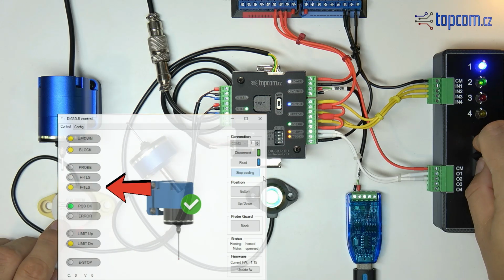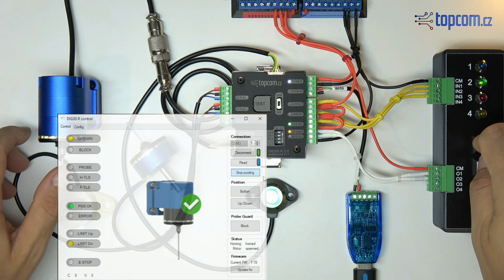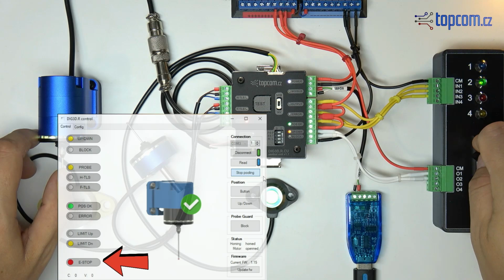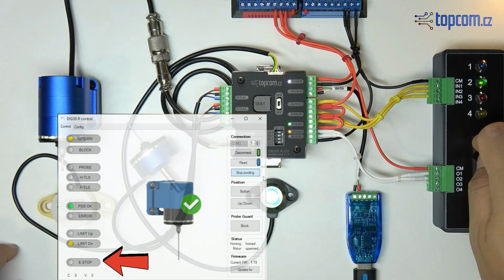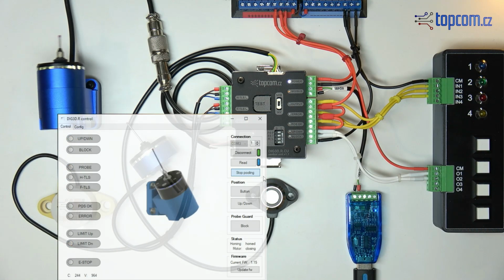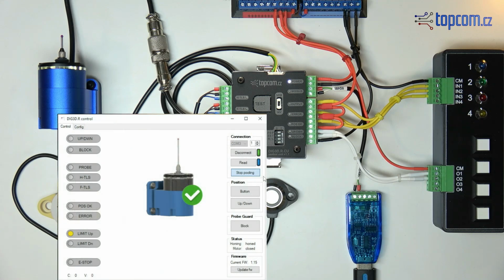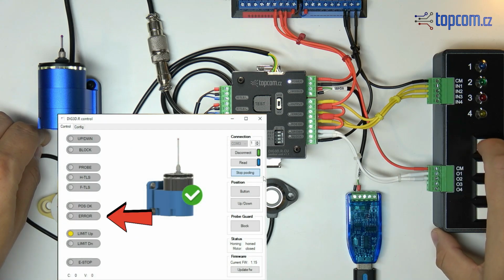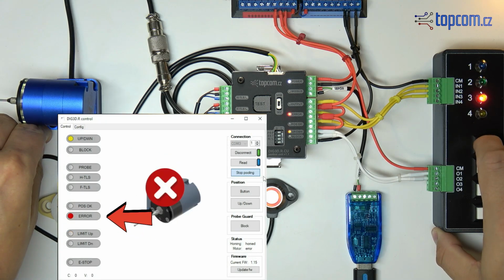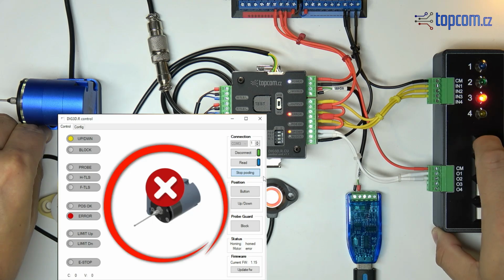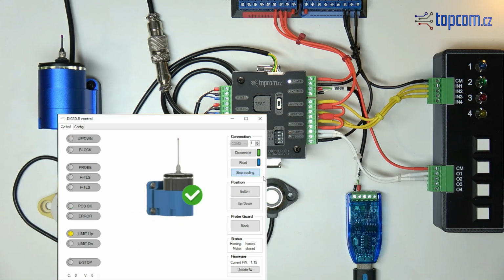Just like the input states, the current states of the control unit's outputs are also transmitted. If the stop signal is activated by the probe guard function, this information is passed on to the master application. If the probe becomes blocked during rotation, the condition is indicated by the error output and is also visually represented in the application. In addition to status monitoring, Modbus communication also allows probe control.